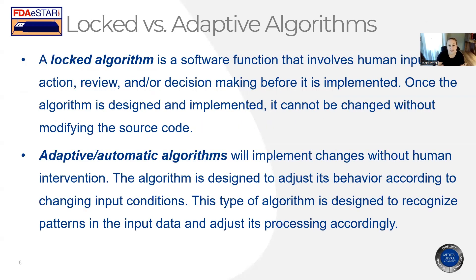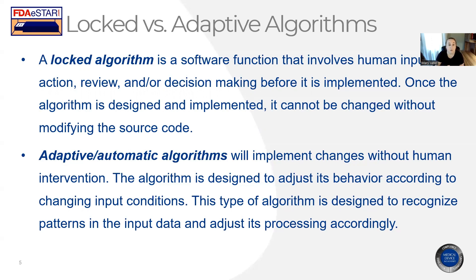PCCPs cover both locked and adaptive algorithms. A locked algorithm is a software function that involves human input, action review, or decision making before it is implemented — once the algorithm is designed, it cannot be changed unless you modify the source code. Whereas adaptive or automatic algorithms implement changes without human intervention; the code is written such that the algorithm adjusts its behavior according to changing input conditions and is designed to recognize patterns in the input data and adjust its processing accordingly. Both of these are covered within the scope of what can be proposed in a PCCP, and you would just need to specify exactly which it is in your detailed description.